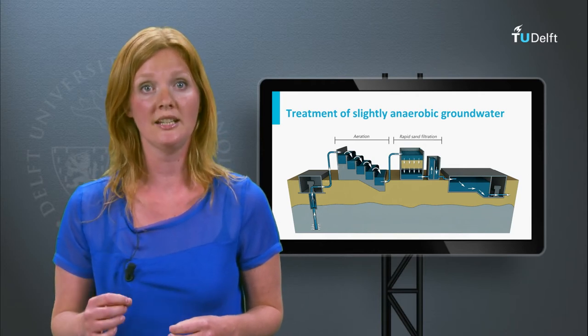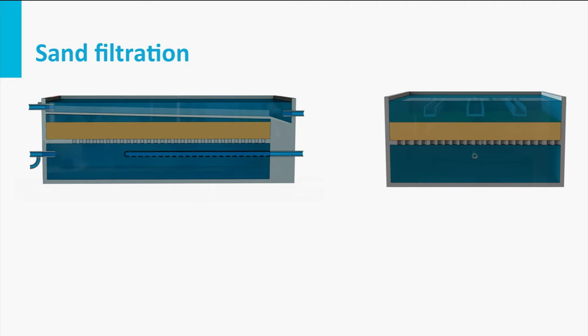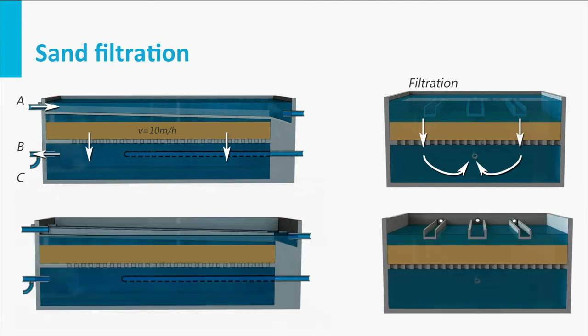Oxygen is also needed for the oxidation of ammonium and manganese. Aeration is followed by sand filtration, where the oxidized ferric iron hydrolyzes to iron hydroxide flocs, which are removed by filtration in the sand bed. Manganese undergoes a partial chemical and biological transformation, while ammonium is biologically degraded by bacteria to nitrate. The growth of these bacteria in combination with the iron and manganese flocs results in an increase of filter resistance, and backwashing is needed to prevent clogging.